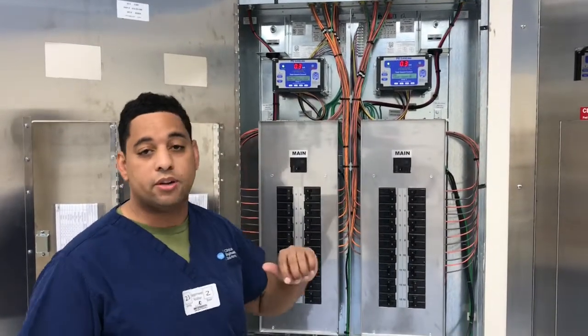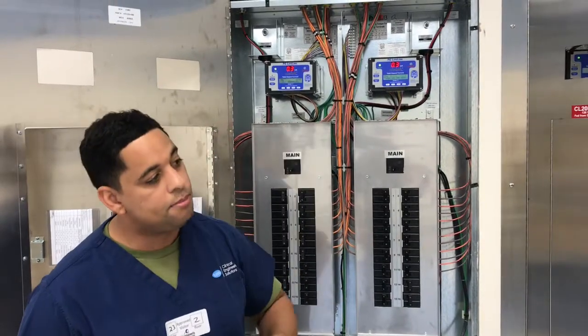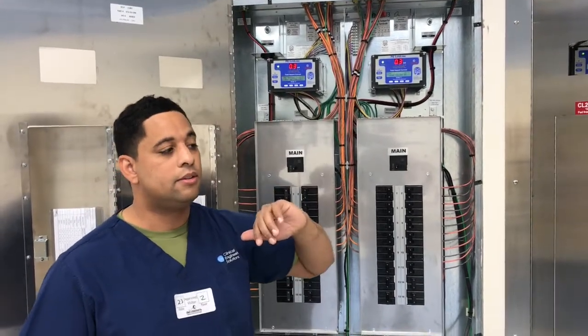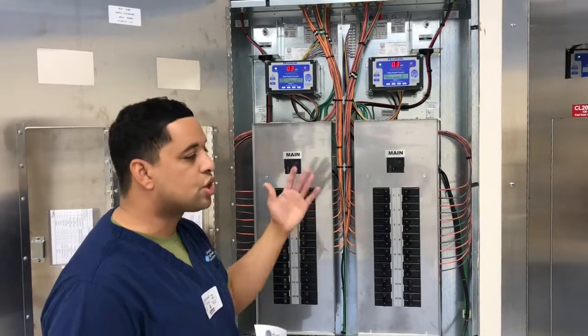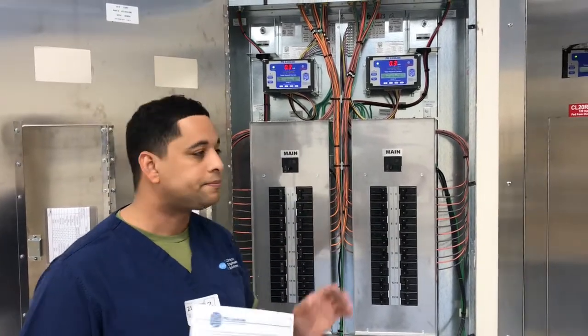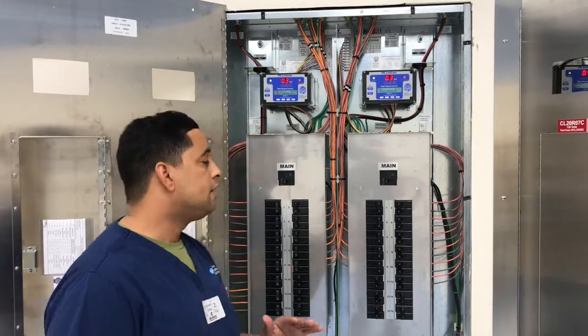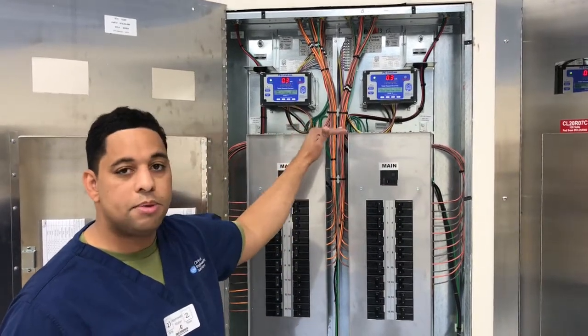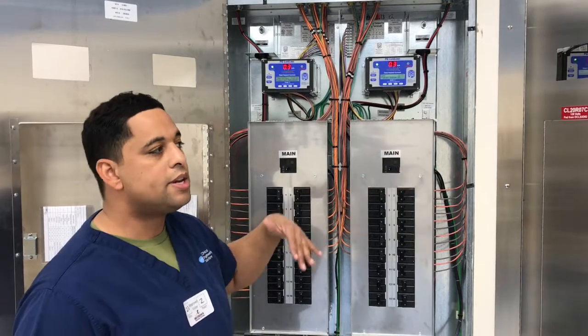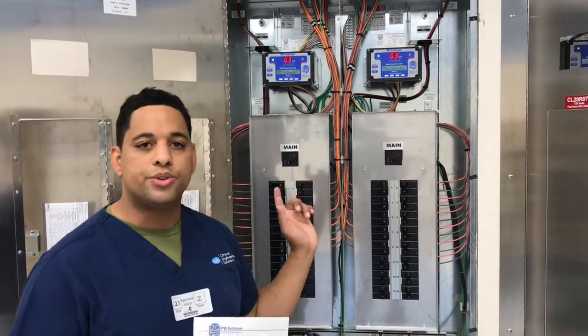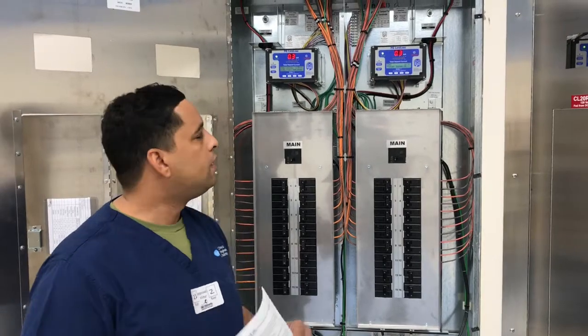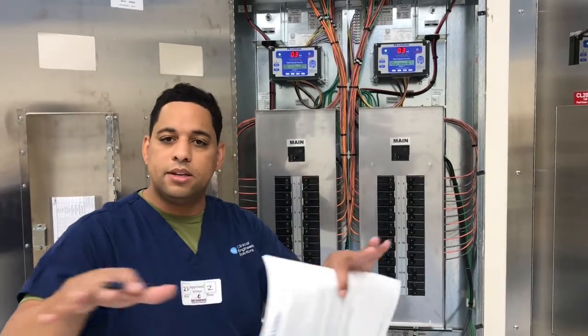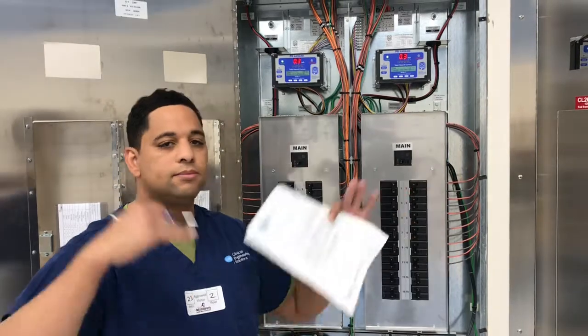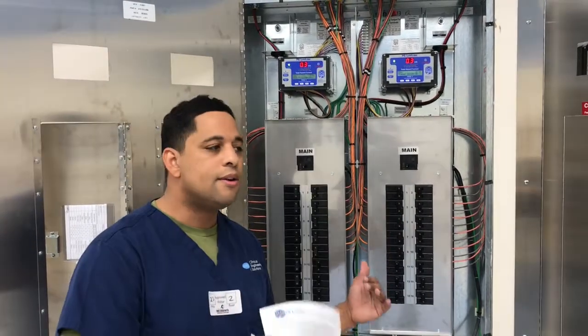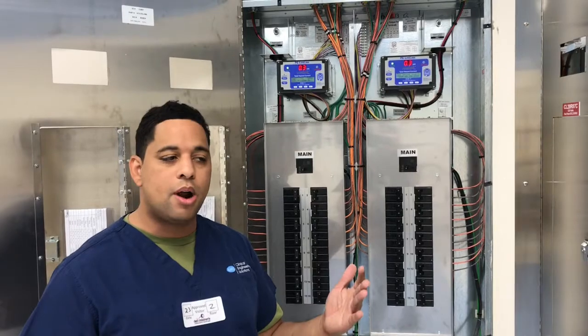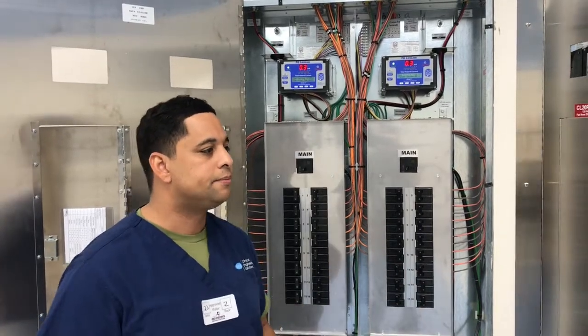So the alarm is critical. Please pay attention to the alarm. It's your only indicator that will tell you that there's an electrical problem in a room that needs to be addressed. Now keep in mind that because of the grounding being immediately grounded, there is not an immediate danger if it goes off. However, whatever is being done here in the room can be finished, and then facilities can come in and find out which device is causing the problem and fix it.